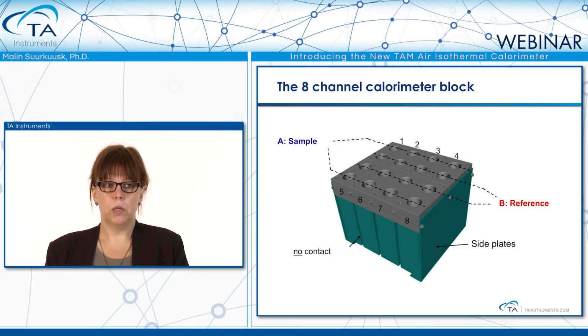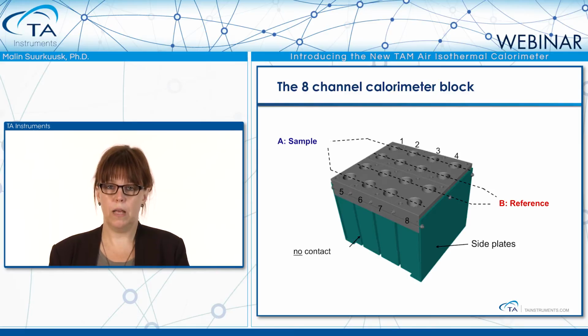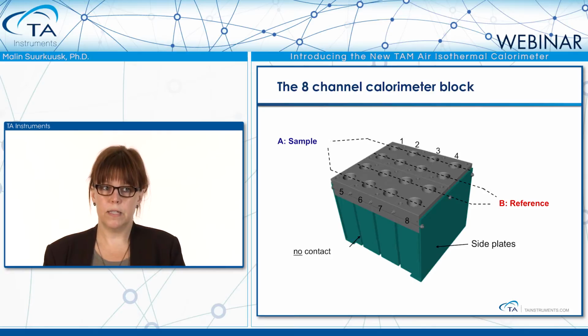And you see in the bottom, that says no contact. That's where the primary heat sink is, and the sample is actually standing onto that. There is no contact between the calorimeters in the bottom part, so we will minimize the crosstalk between the channels. In the top, all the secondary heat sinks are connected together to transfer away any disturbances from the surrounding. Also, to minimize heat flow, all the samples, which are in the A sides, are positioned on the outside, and we have the inert references pointing towards the middle.